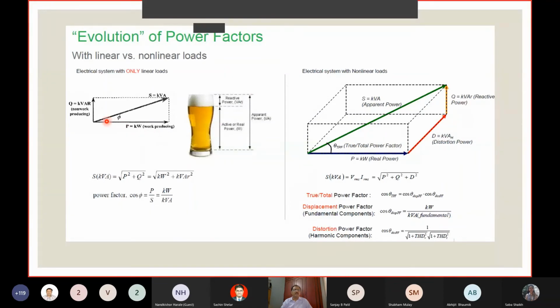So similarly, kVA is what we are contracting to receive from the electricity board. Kilowatt is what we actually put to useful work, and reactive power is the kVAR. This is the classic power triangle where the relationship we denote kVA by S, kilowatt by P, and kVAR by Q. So the relationship is S is equal to square root of P square plus Q square.